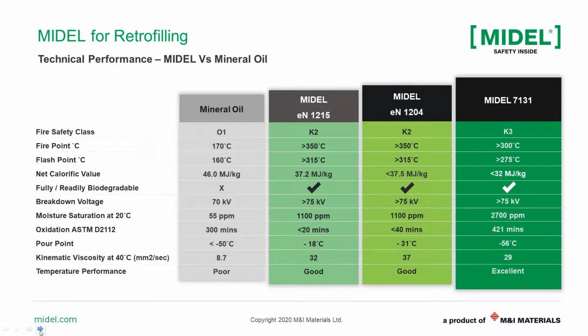The last thing I would like to mention here is the pour points. You can see that natural esters have a low pour point, -18, -31. MIDEL 7131 has a really low pour point, -56, which is sometimes a little bit better than mineral oil. However, to get the right picture, you need to see it together with the viscosity values as well. If we look at the viscosity, you can see that the ester liquids have higher viscosity than mineral oil, and this is why we always need to make some consideration before retrofilling about what the outputs of this transformer could be from a thermal point of view.